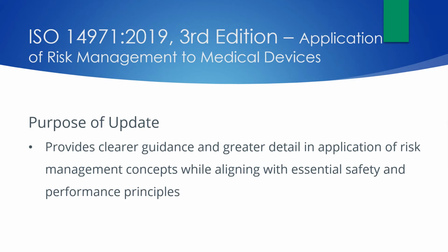ISO 14971 and ISO 13485 are related because they work together to create a QMS that is functional and addresses risk. ISO 13485 is focused on regulatory and customer requirements for medical devices. ISO 13485 also requires risk analysis and record keeping pertaining to any risk. In this area, ISO 13485 looks to ISO 14971 for guidance. ISO 14971 is more detailed when it comes to risk management requirements. Companies should perform a gap analysis between the new and old versions of ISO 14971, identify areas to address, and update processes and procedures as needed to comply.